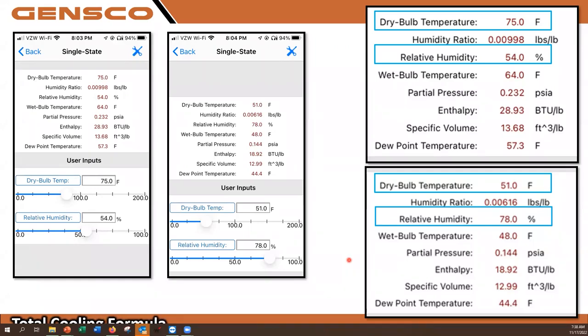Same thing about our coil temperature. In order for us to actually condense and remove moisture, the coil temperature has to be below 57 degrees. This could also be why water is dripping off the front of your unit while it's running, because the dew point temp in the room is 57 and the exit air is 51. My louvers are much colder in the front of that unit. Eventually, over a little bit of time, they'll reach 51 degrees and any moisture in the room will start to build up on them. So these are good numbers to use. And if you don't have a psychrometer, you can get a nice digital one for $100 or less.